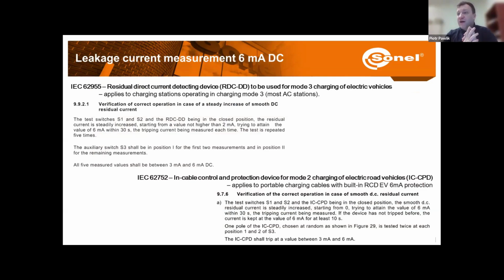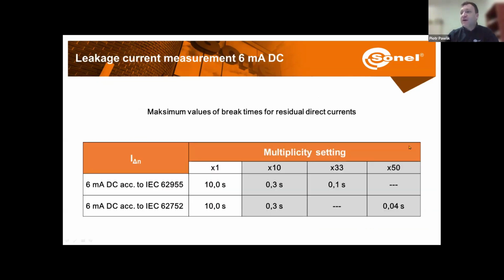Then we'll look into the IEC 62752 to make sure that our protections will work for the DC leakage currents above 6 milliamps. And here, as per these standards, we can see how we need to check the breakers and what would be the maximum values of the times for multiplication of the nominal current.